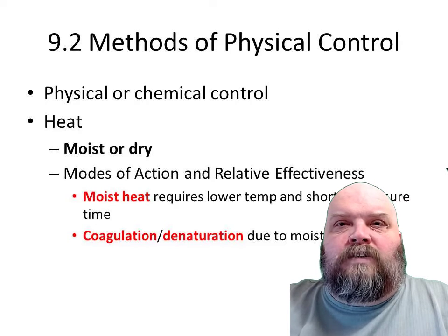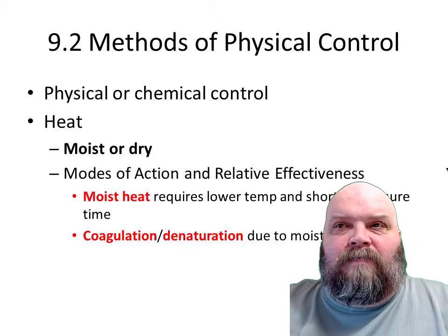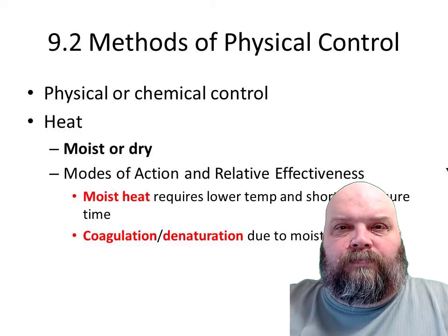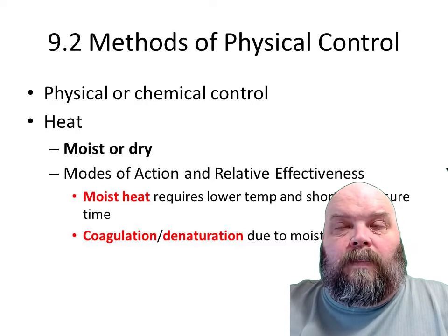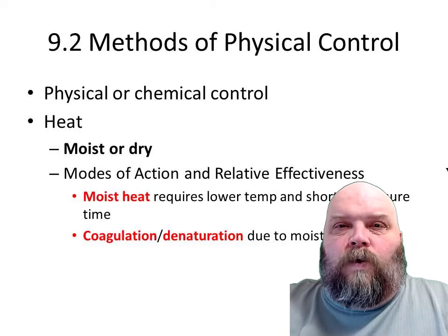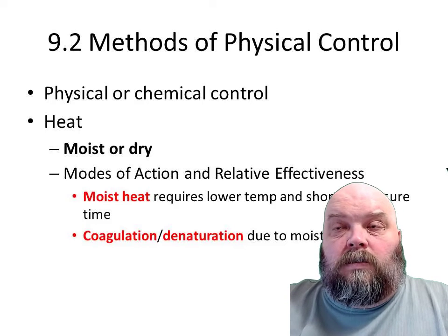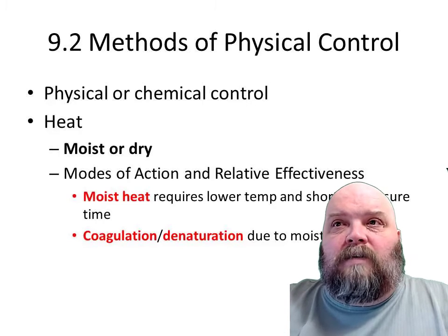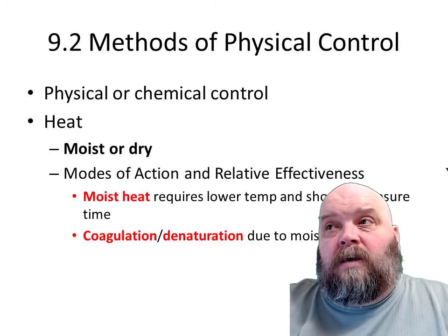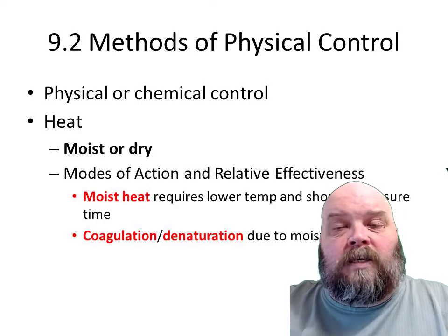You raise the pressure in a sealed environment, up to 4 or 5 times atmospheric pressure. By doing so, you're also able to raise the boiling point of water. So instead of 100 degrees Celsius, it's now going to be 110, 120. You're getting more heat out of the water and the water vapor, which can penetrate into the nooks and the crannies better.